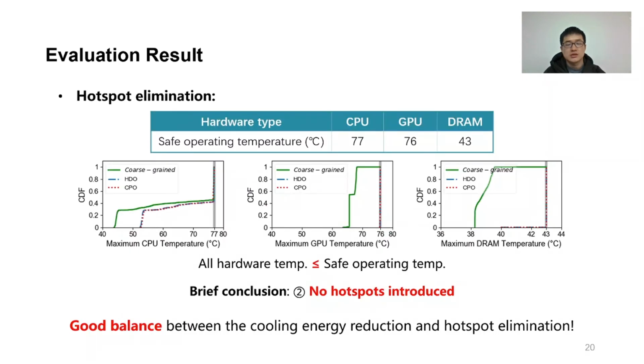Our solution is also effective in eliminating hotspots. We define the safe operating temperature of 3 hardware types according to their thermal design power. As we can see, although the maximum hardware temperature gets higher by applying our strategies as compared to the coarse-grained strategy, no hardware component runs above its safe operating temperature. In summary, our solution achieves good balance between the cooling energy reduction and hotspots elimination.